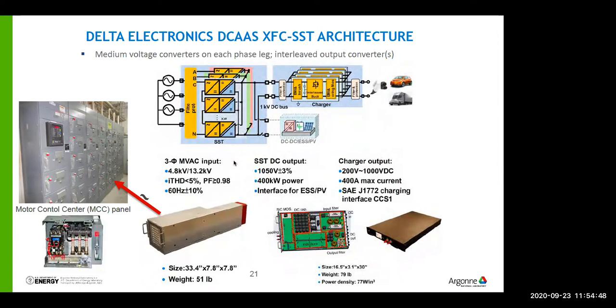Basically that block directly above it that says SST, these are solid state transformer modules. They're 50 pounds each, so you can pick up each one and put it in the hole. And you run a whole bunch of them in parallel. You can see each one per phase. You connect each one to a different phase leg, and then you have a whole bunch in parallel. You can just imagine row after row, rack of these. When one fails, you pull out the one that has failed, almost like a valve, and you put it back in.